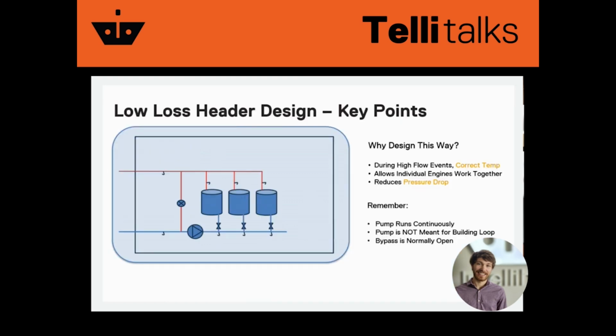Okay, now, why are we designing the unit this way? Well, when I have a 50 GPM event occur across my floor mount unit, rather than trying to force 50 GPM through my 3 heat exchangers, which I won't be able to do, I allow some of that flow to go through my bypass. This is a core tenet of our modular design because it allows multiple heat exchangers to work together in order to meet the capacity of the system without dropping all of the pressure that you would if you had to force that flow through your heat exchangers.